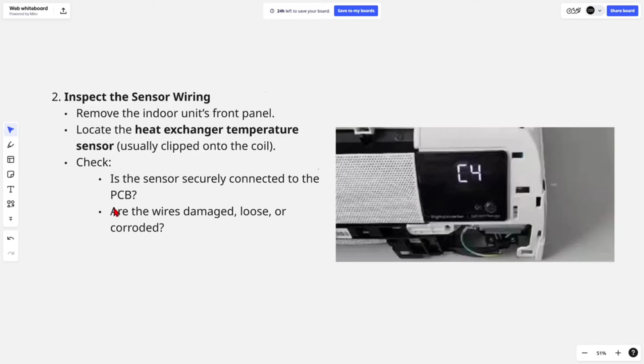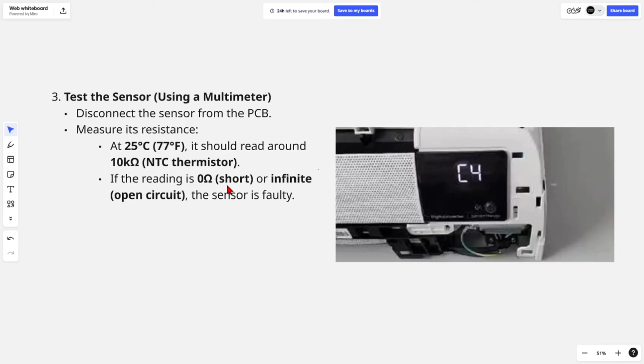Step 3, test the sensor. You can do this using a multimeter if you have one. Disconnect the sensor from the PCB and measure its resistance at 25 degrees Celsius or 77 degrees Fahrenheit. It should read around 10k. If the reading is 0 or infinite (open circuit), the sensor is faulty.